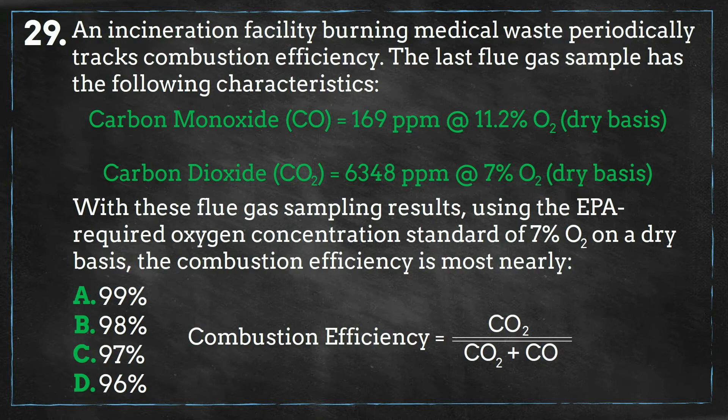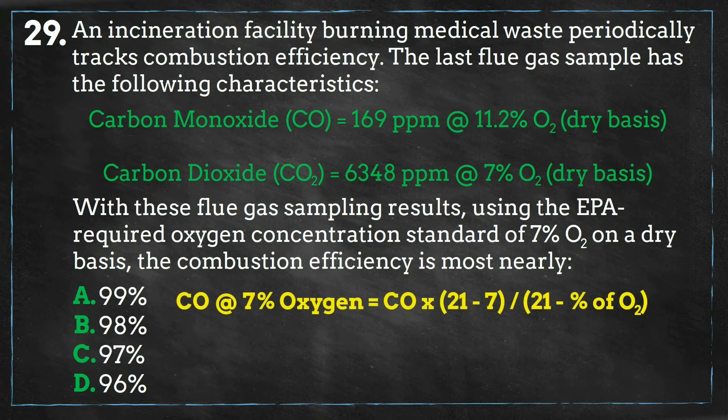So we have our two concentrations, but remember that the EPA requires that all concentrations are used reflecting the condition of 7% oxygen on a dry basis. Our carbon dioxide measurement meets this standard, but our carbon monoxide data does not. So we will need to convert it using this equation.